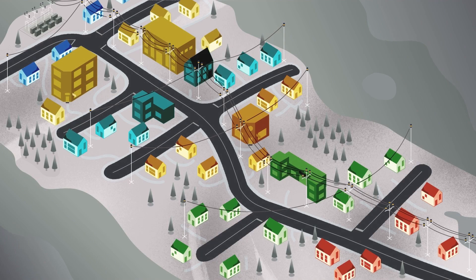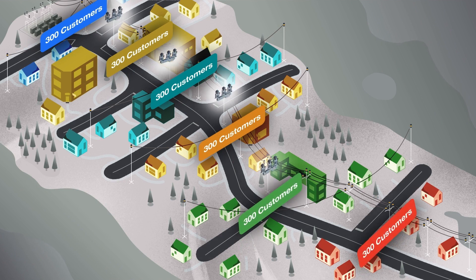So how does it work? Let's take this feeder with 1,800 customers and divide it into 6 segments, leaving 300 customers per segment. With the Pulse Finding Technique, all IntelliRupter devices can use the same TCC curve.